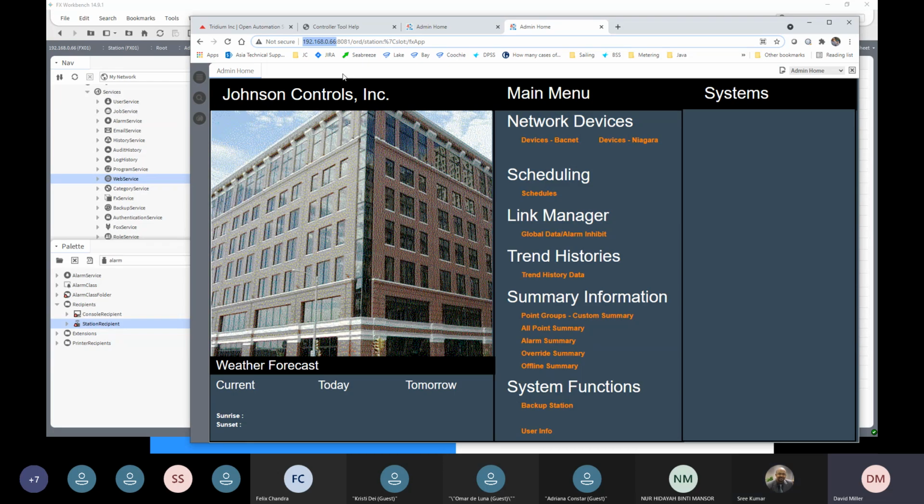If you have the demo Workbench, which is intended as an engineering tool, then the license expires every year and gets renewed every year. And it's got all of the features activated. It's a test engineering workstation for testing. That's what I'm using for both of these JACEs at the moment, is demo, and every year it gets renewed. And so that's why I can't take it and put it on a project, because in a year's time it'll stop working.